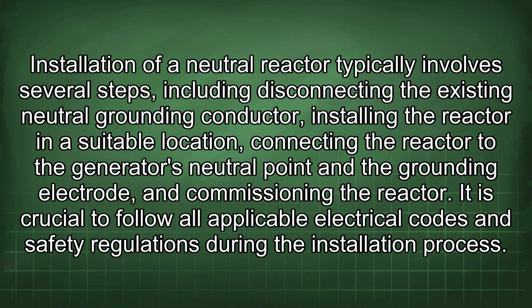Installation of a neutral reactor typically involves several steps, including disconnecting the existing neutral grounding conductor, installing the reactor in a suitable location, connecting the reactor to the generator's neutral point and the grounding electrode, and commissioning the reactor. It is crucial to follow all applicable electrical codes and safety regulations during the installation process.